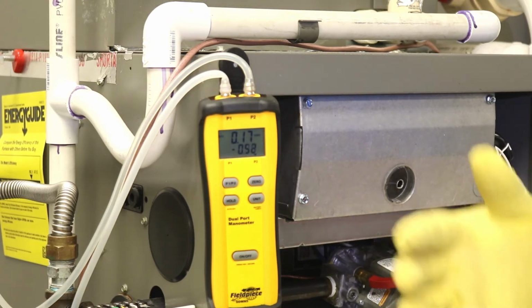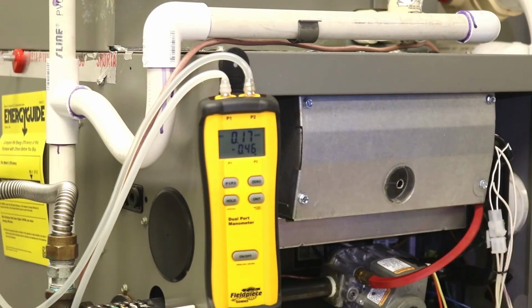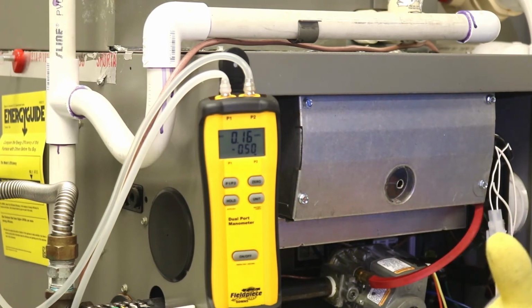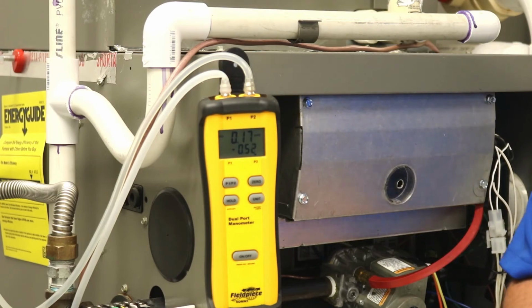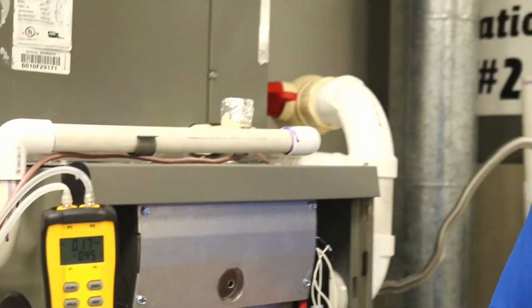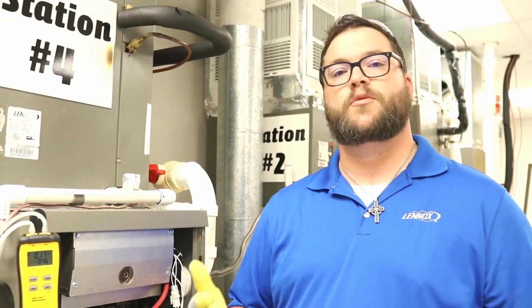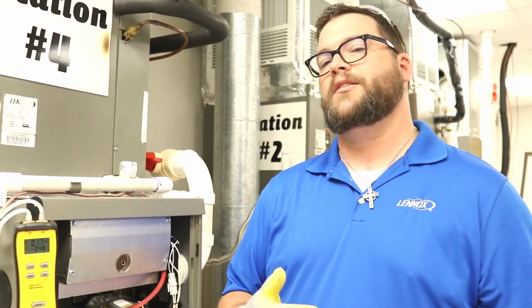So making sure that you know how to check static pressure to verify that it's within that range is very, very important. This is something that when you're doing a maintenance or a service visit, it's very important to be able to explain to a customer, hey, this is what's going on with your system, and this is why I don't believe that your compressor is the problem, or this is why I don't believe that the equipment is low on refrigerant. There are lots of other pieces of the puzzle. Most often you're going to find that airflow is a major issue within the HVAC system.